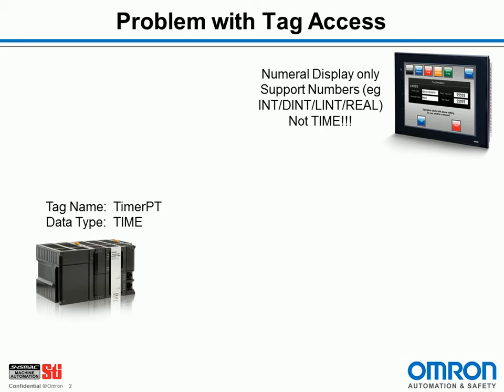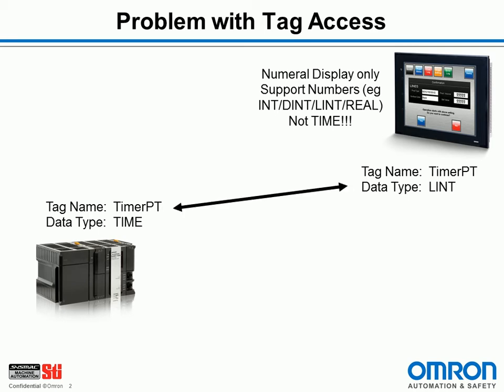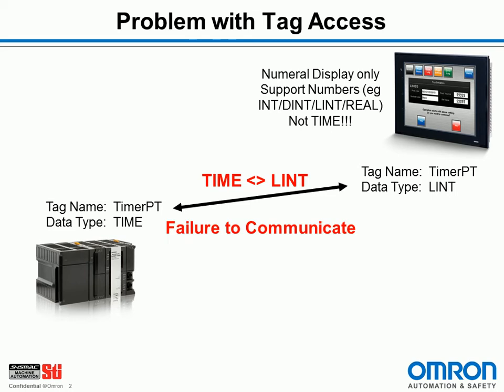So if I was to put my timer PT tag into that object, I would set its data type to be long integer, let's say. And when I try and communicate, not only does it check the tag name, it also checks the data type. And it says, time is not equal to long integer, and therefore the HMI does not properly communicate with the PLC.